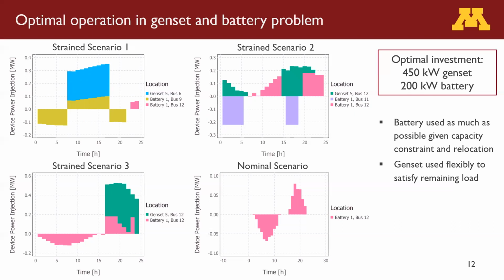This is particularly noteworthy because this flexible operation of the genset enables the 2 devices together to operate in ways that the multiple batteries could not operate on their own. So again, scenario 2 really highlights this behavior, because in this case, the genset operates throughout this extended time period between hour 15 and hour 22, where if it were a battery, there would not be enough time for it to recharge by the end of the time horizon or in this period here. But because it's a genset that doesn't need to recharge, it can satisfy all of this additional demand that the battery can't quite cover without having any sort of operational restriction or constraint due to recharging and relocating.